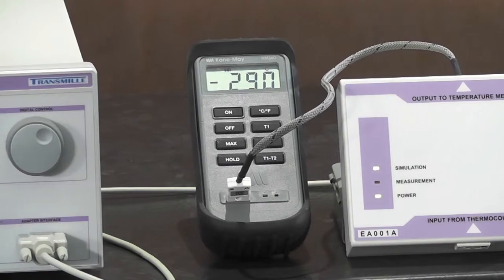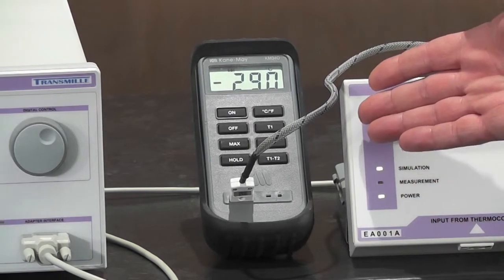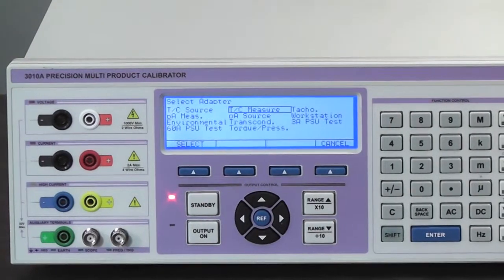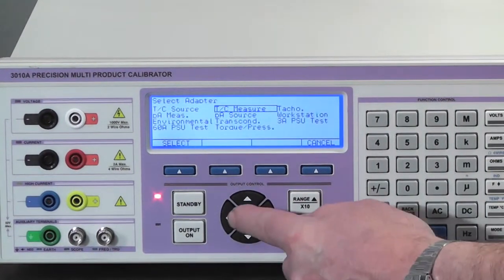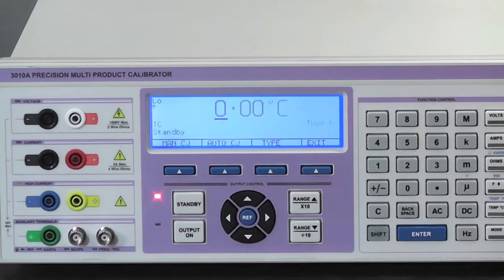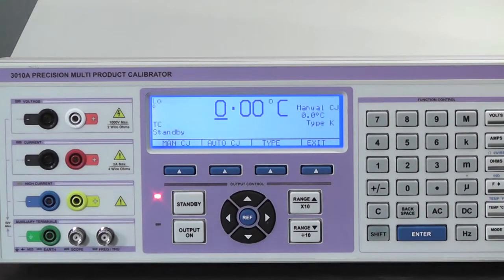To simulate temperature begin by connecting the unit under test to the thermocouple adapter. Then proceed to select TC source. Using the soft key select auto CJC.